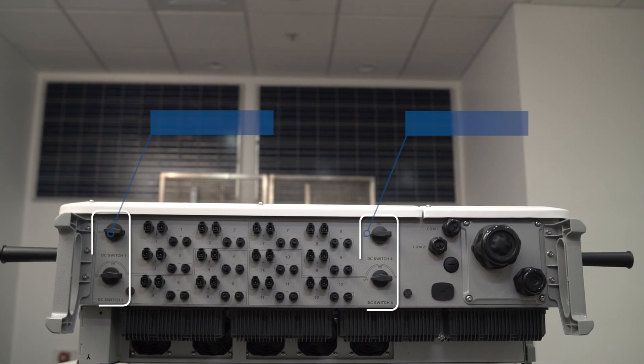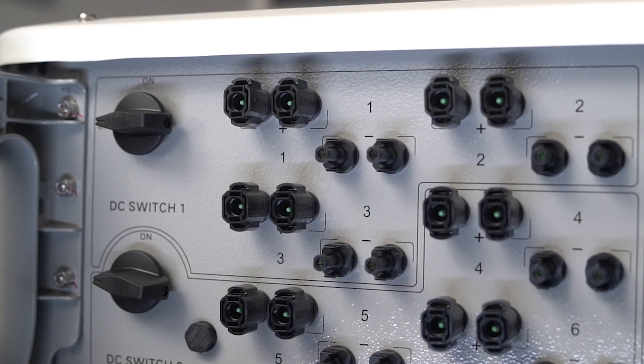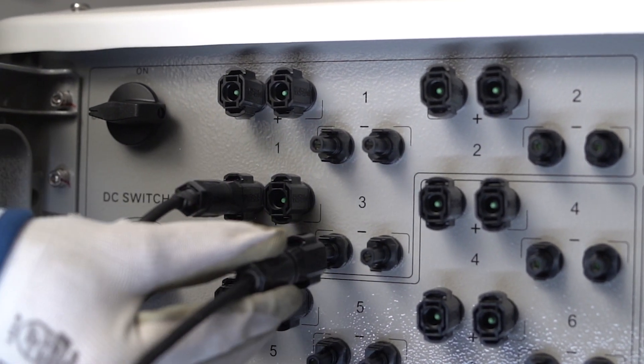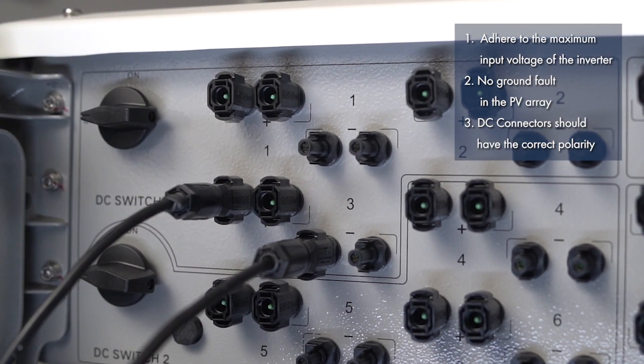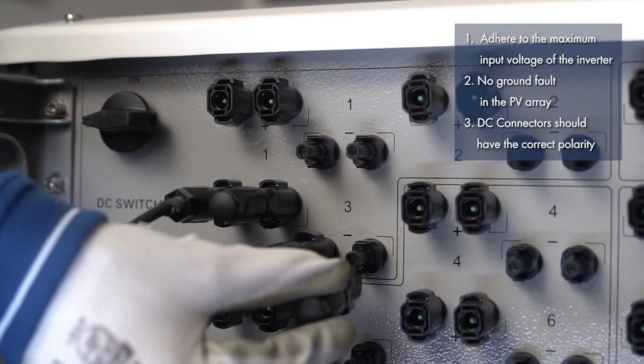Switch off the inverter's two DC load brake switches and measure the PV array voltage. Connect the assembled DC connectors to the inverter and ensure they are snapped properly into place. For unused DC inputs, insert the DC connectors with sealing plugs and ensure they are securely placed.